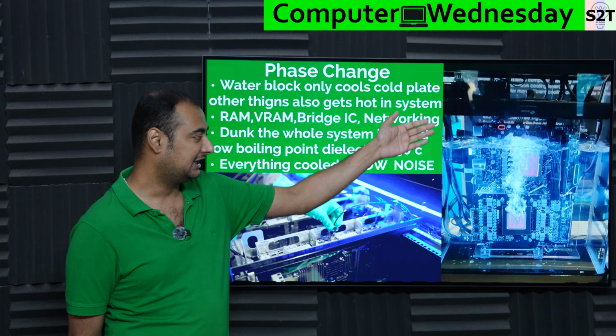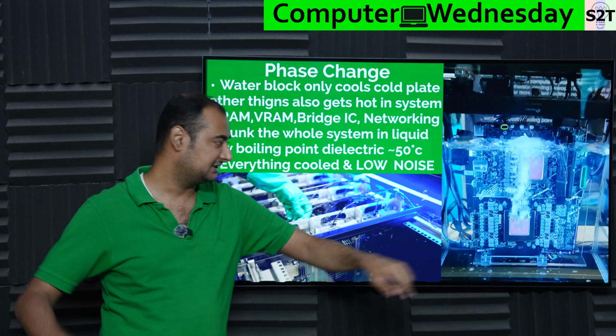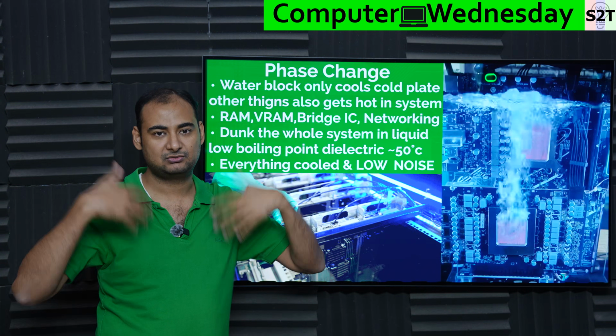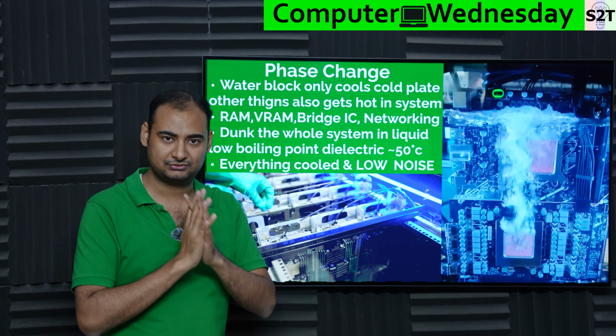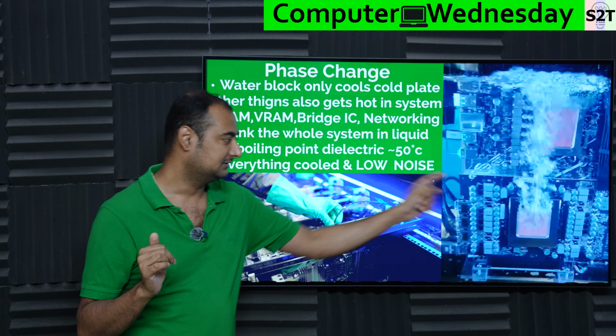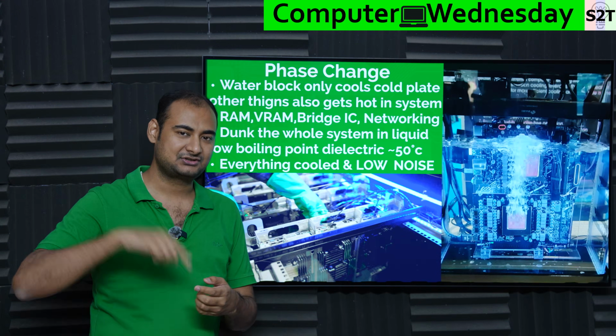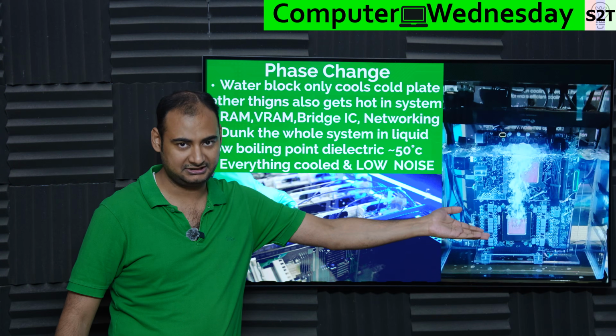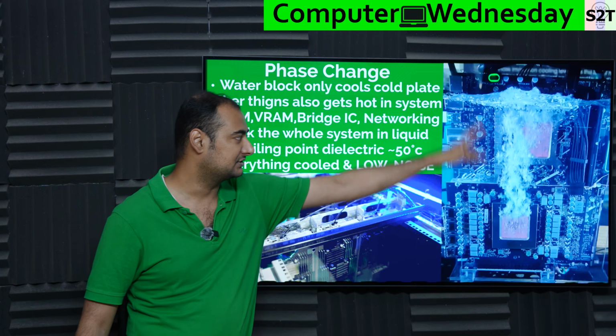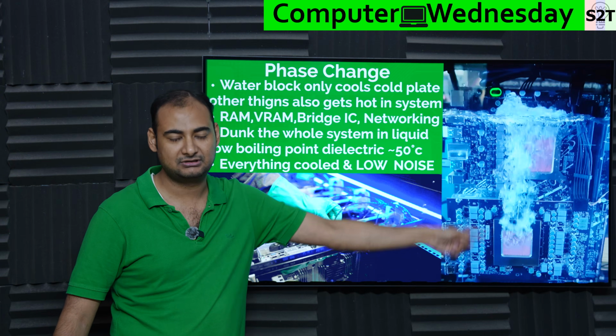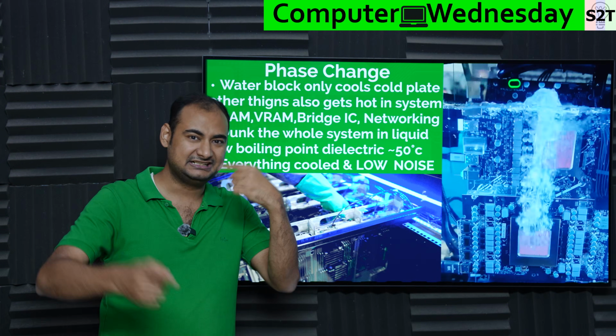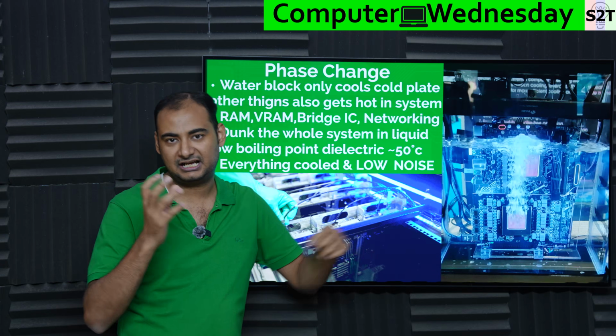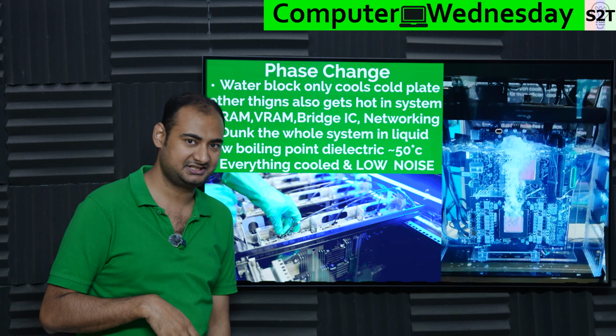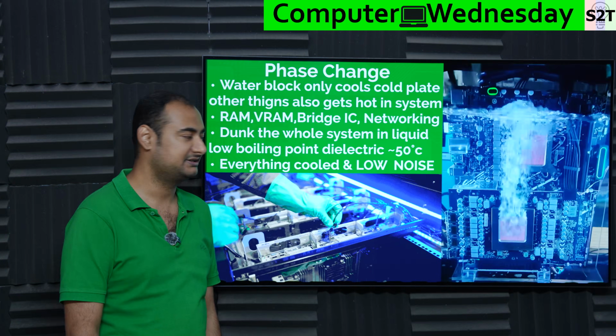Why 50? The idea is you dunk everything in it. Let's say the VRAMs are below 50, liquid is circulating around it, fully submerged, so it's at equilibrium. The CPU dumps heat, temperature goes above 50, the liquid boils, turns into steam, and goes away. New fresh liquid comes in and does the same thing. Because it's a physical leaching of energy, the temperature of the die doesn't even exceed like 60 or 70 degrees Celsius. It all remains in a reasonable range.